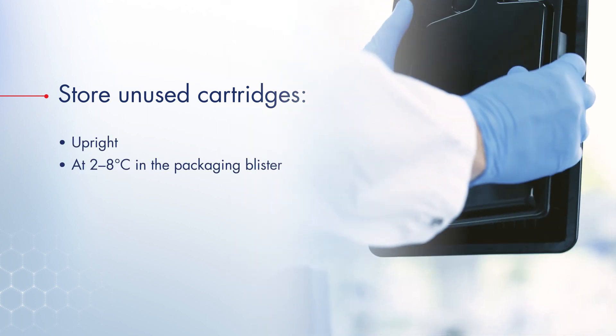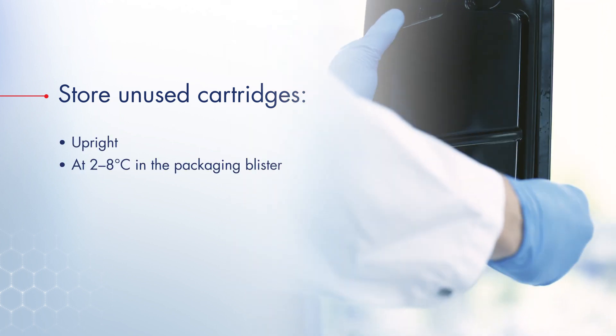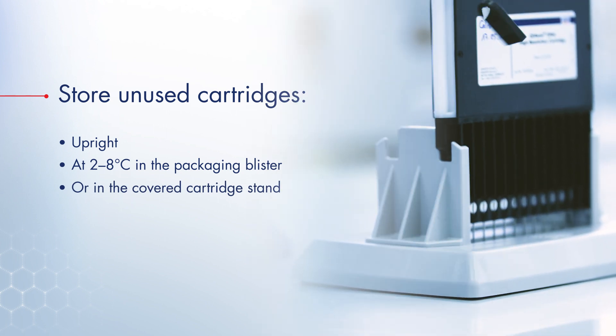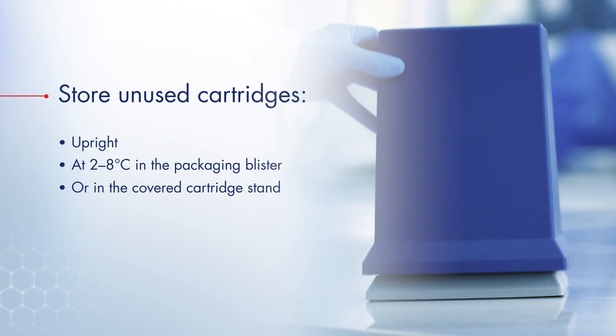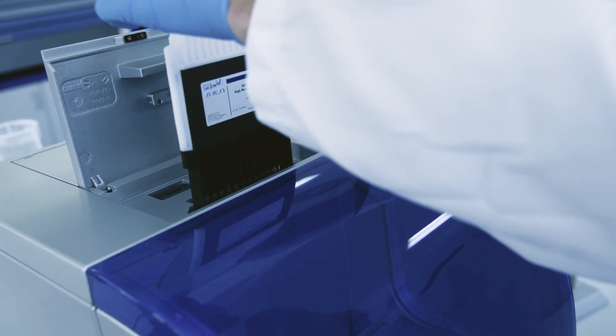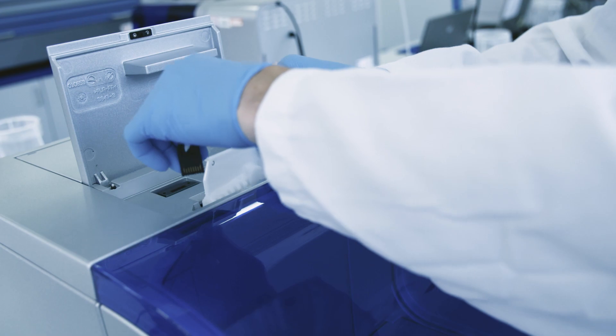Unused cartridges should always be stored upright at 2-8°C in the packaging blister or covered cartridge stand to protect the gel from drying and direct light. If the cartridge is stored in the QIAxcel Advanced, the instrument should always be switched on.